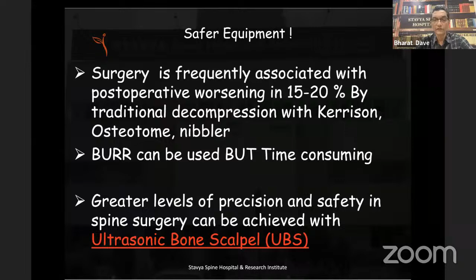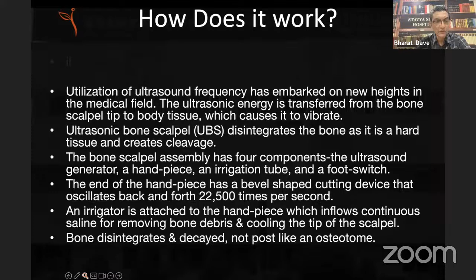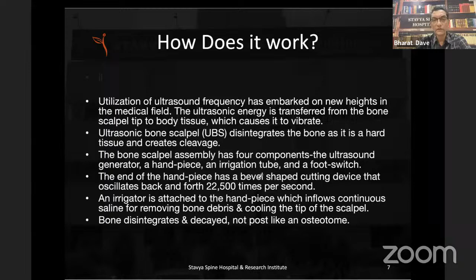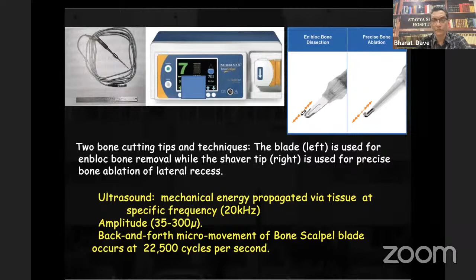How does it work? It works on ultrasound frequency, which gets converted into cutting by the piezoelectric effect. The handpiece has piezo crystals and it converts that into 22,500 vibrations per second, which is something to remember. It has an irrigation tube, and the handpiece goes into the console of the bone scalpel. It doesn't cut with a to-and-fro movement; it cuts like a vibration, at 22,500 cycles per second. That is how it cuts the bone.